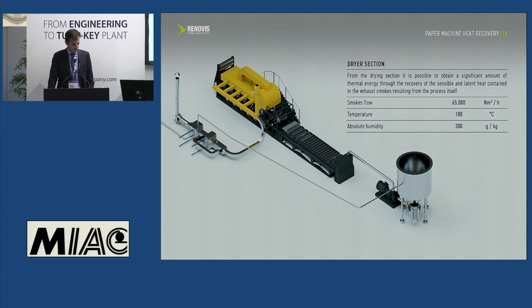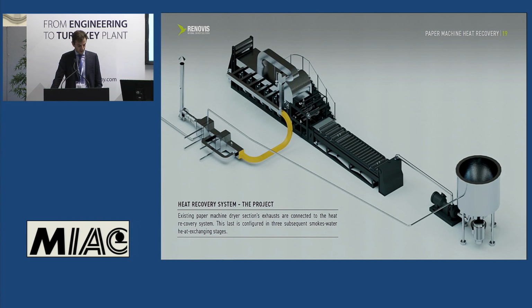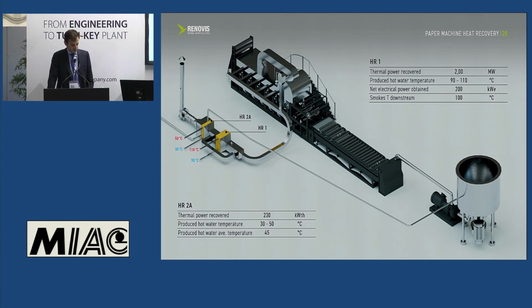This slide shows us, in fact, how significant are the flow rate, temperature, and humidity of the fumes coming out from the drying section of the paper machine. In our project, existing paper machine dryer section exhausts are connected to the heat recovery system. This is configured in 3 subsequent smoke-water heat exchanging stages. The first stage generates superheated water in a closed circuit at 110 Celsius degrees, which returns to 90 Celsius degrees as end cycle temperature. The recovered thermal power is 2 megawatts.